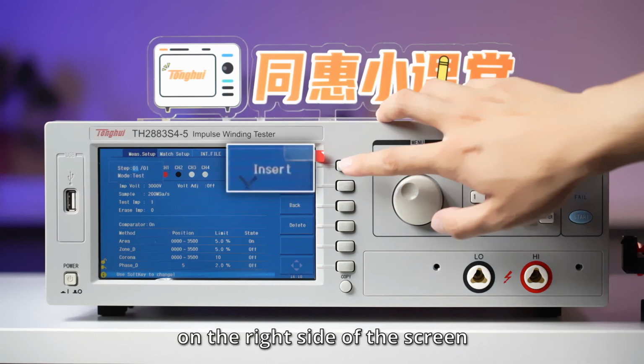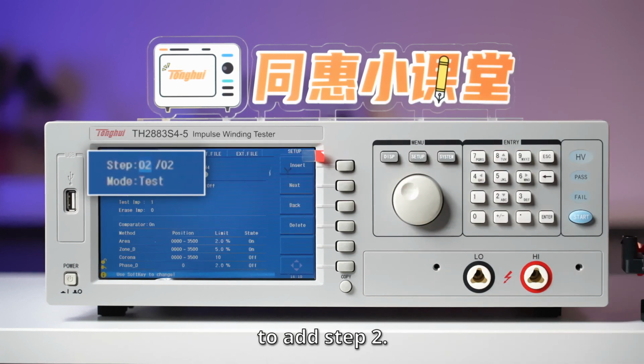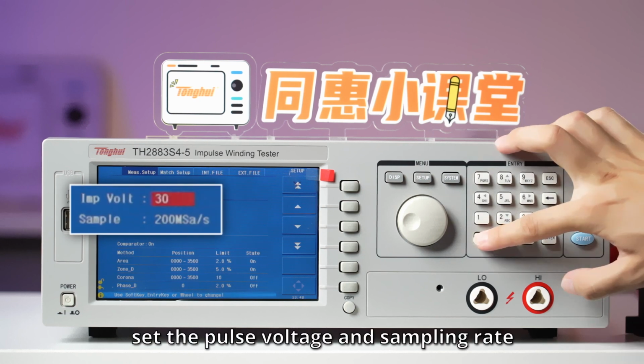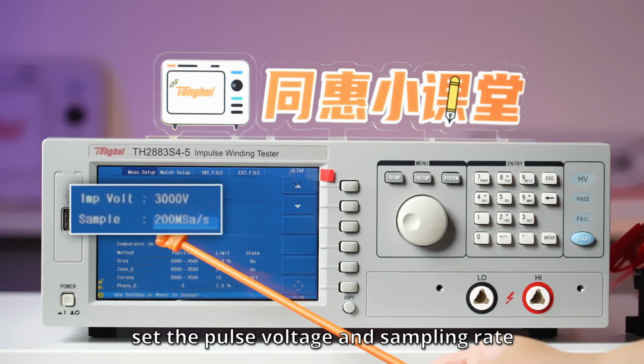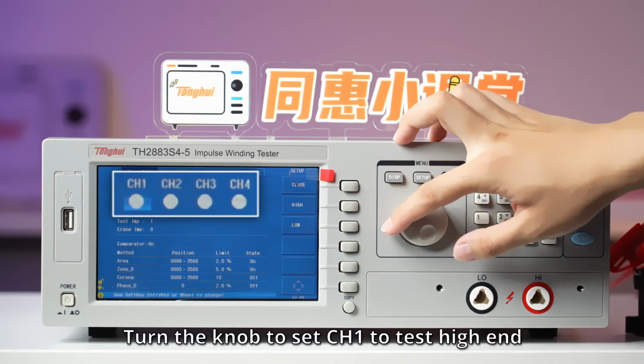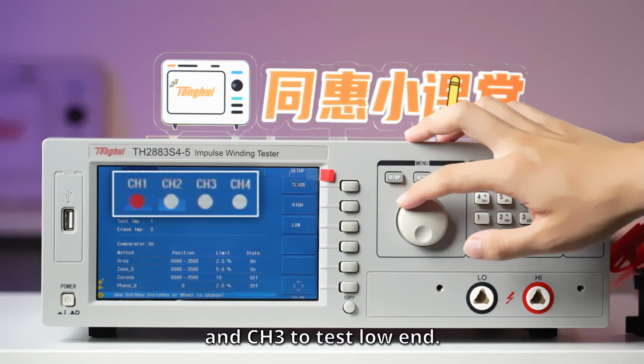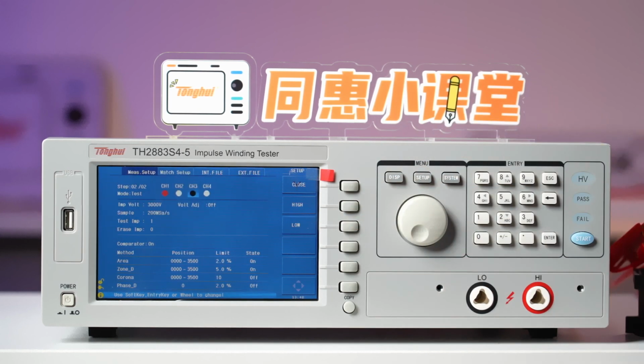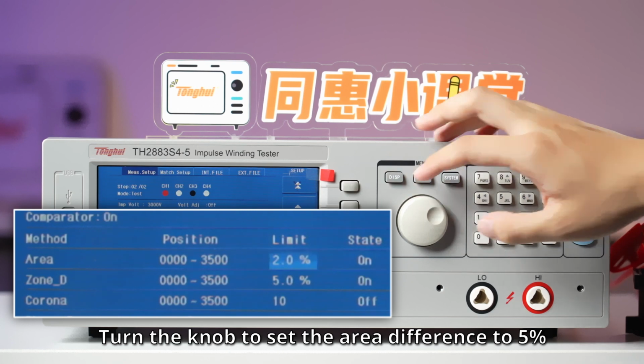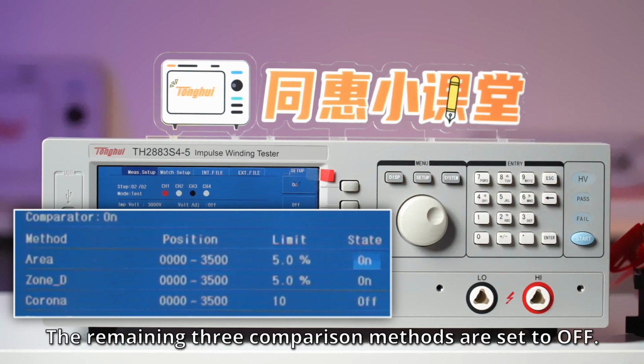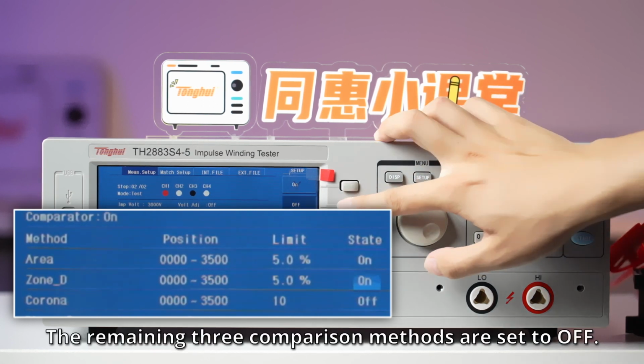Click the Insert button on the right side of the screen to add Step 2. Set the pulse voltage and sampling rate. Turn knob to set Channel 1 to test high end and Channel 3 to test low end. Turn the knob to set the area difference to 5%. The remaining 3 comparison methods are set to off.